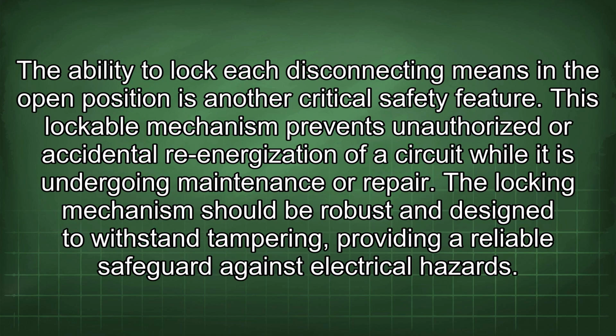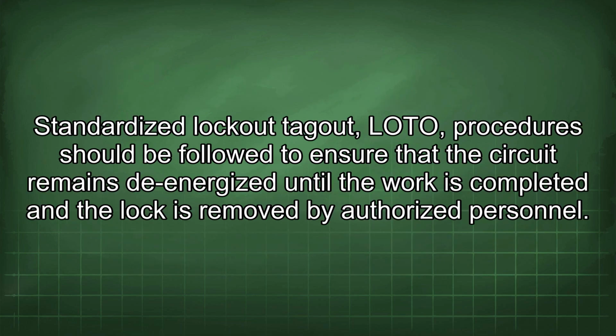The ability to lock each disconnecting means in the open position is another critical safety feature. This lockable mechanism prevents unauthorized or accidental re-energization of a circuit while it is undergoing maintenance or repair. The locking mechanism should be robust and designed to withstand tampering, providing a reliable safeguard against electrical hazards. Standardized lockout-tagout, LOTO, procedures should be followed to ensure that the circuit remains de-energized until the work is completed and the lock is removed by authorized personnel.